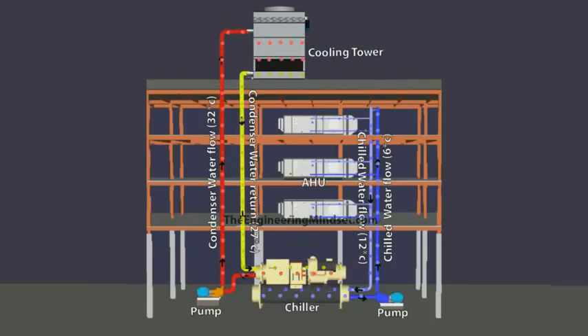So you can see it's fairly similar to the water-cooled chiller. This is a setup for a water-cooled chiller here, where it's got a different loop which goes off to a cooling tower, and you've got more pumps, etc. So you can see why the other version is more popular, but the water-cooled chiller is much more efficient.